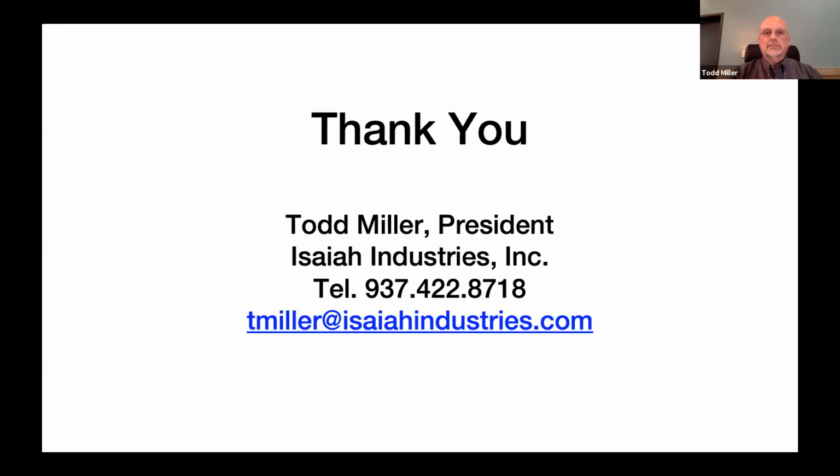Oh, we might have another question here. Let me look. Could you speak a little more about heating a metal building and the moisture that can be put into the building by using propane, natural gas versus other heating sources? I'm not sure I can talk directly to that situation, Gary. That's not a world that I typically live in, but the same things apply. Warm, moist air on a cold surface is going to condense. So if you're watching the moisture levels inside the building, anytime you're seeing ambient moisture inside a building of 30% or more, that's pretty high. And so that's the time to think about dehumidification, maybe an air makeup unit, something in order to get that moisture level down a little bit.